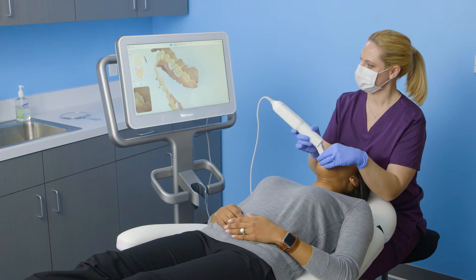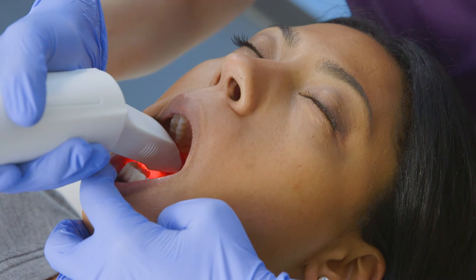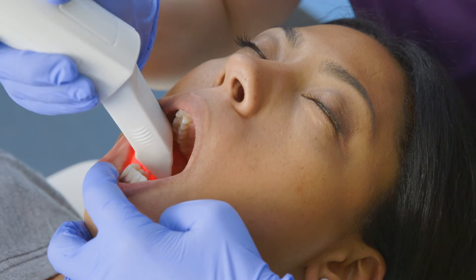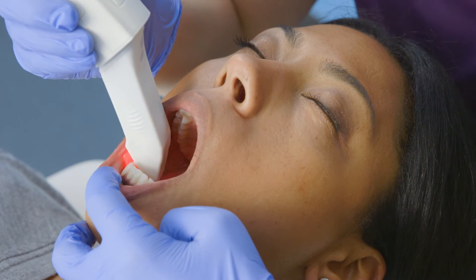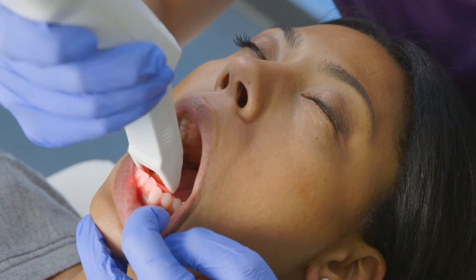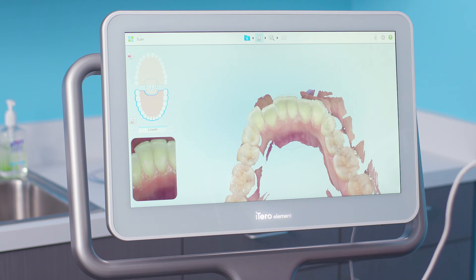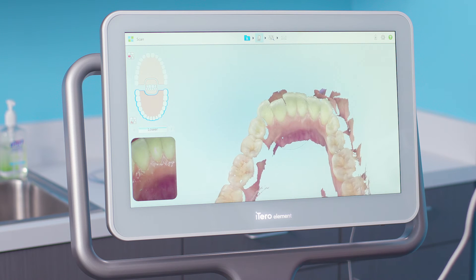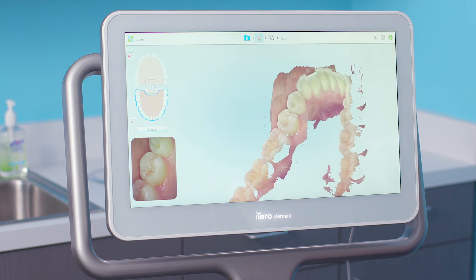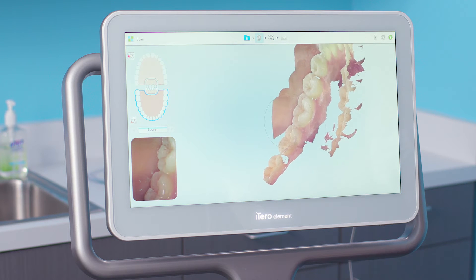Once I've reached the most terminal tooth, I'll rotate to the lingual. I'll bring the cable end of the wand out to the side and maintain a 45 degree angle of the wand tip to the lingual surface. Using a twisting motion, I'll continue around the entire arch, being sure to capture the inner proximal anatomy of the entire lingual surface.